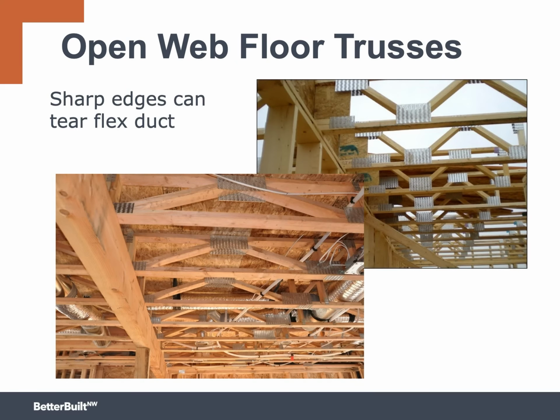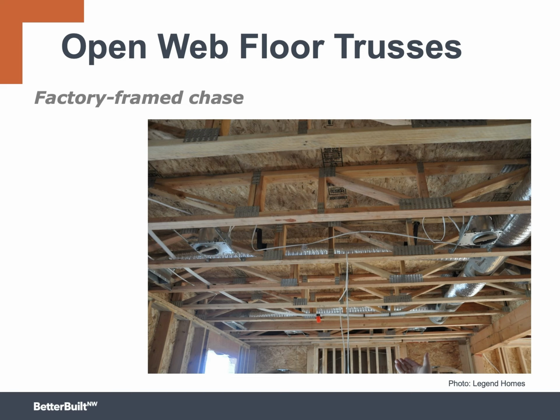Watch out for the sharp edges on truss plates. Pulling flex duct across a sharp edge could tear it. Trusses can be made with a rectangular duct chase built right in. It's relatively easy for the truss manufacturers to do this. This may be necessary if your duct diameter is rather large. You just have to specify where the duct chase will be and how big it is. It's a very inviting space to run all kinds of other things as well as ducts.